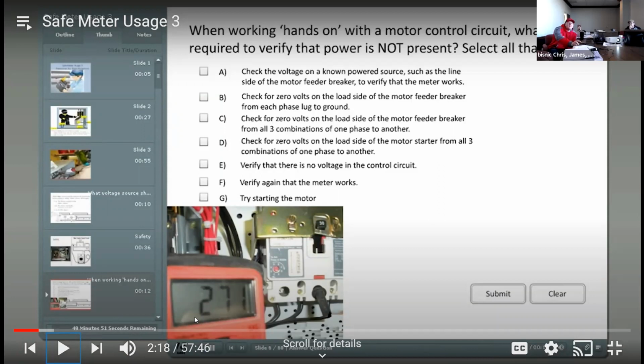I don't know, if you had a ground issue though, and you weren't grounded well, you could still see it phase to phase, but not see it to ground. Okay, well, let's talk about that a bit. I would still go phase to phase to verify you got a ground. Well, you would have a ground because remember up here, we checked from a known power source. Oh, okay, gotcha. I do it anyways, just to cover my own hind end. That's kind of what I do too, ground to phase.